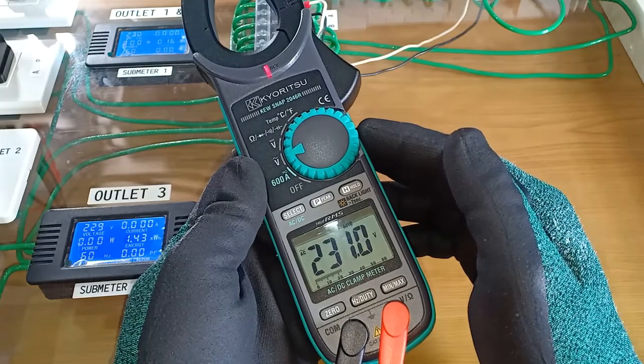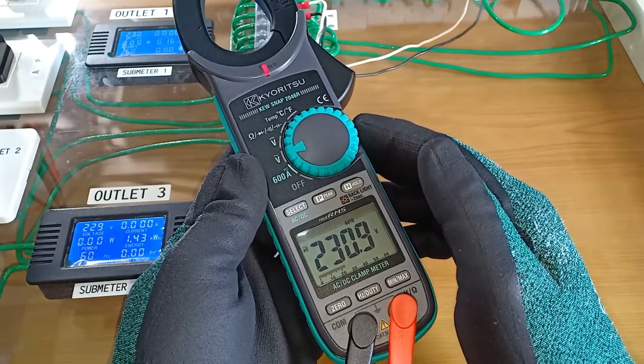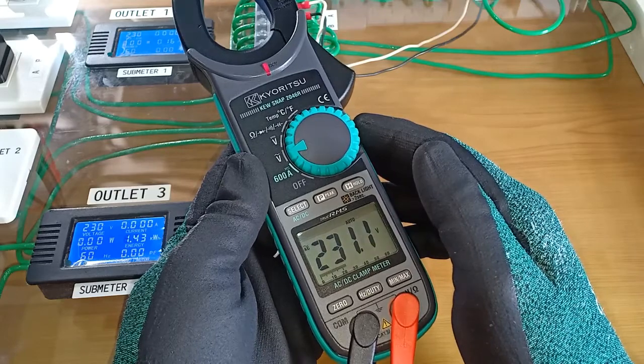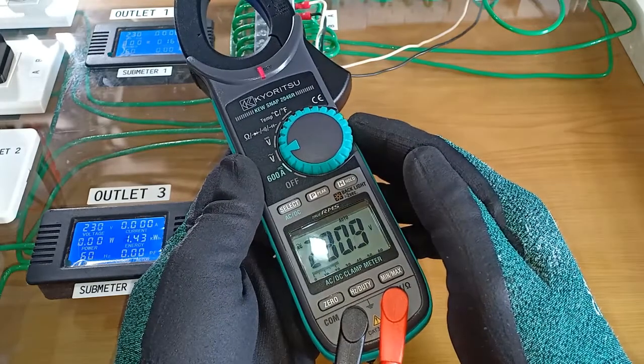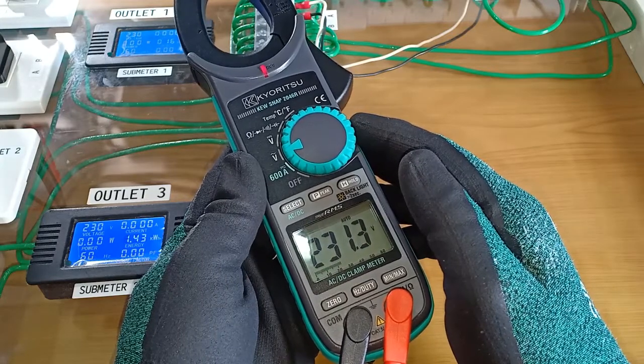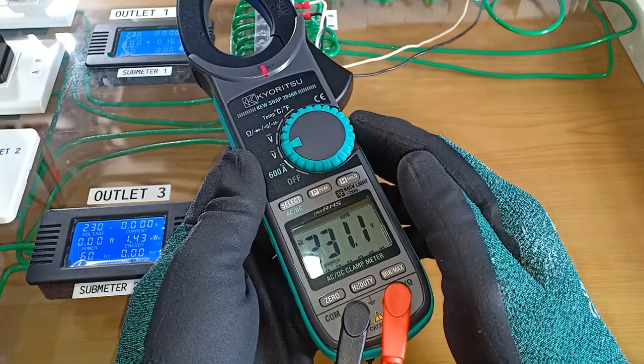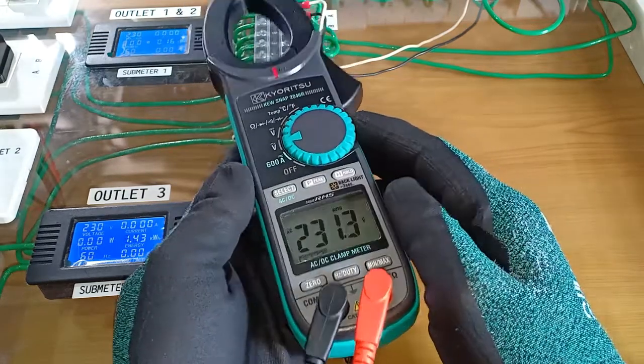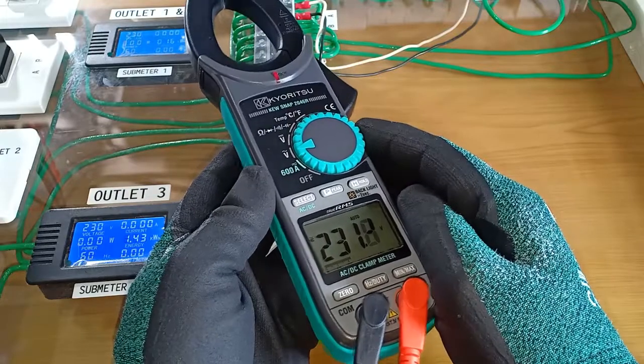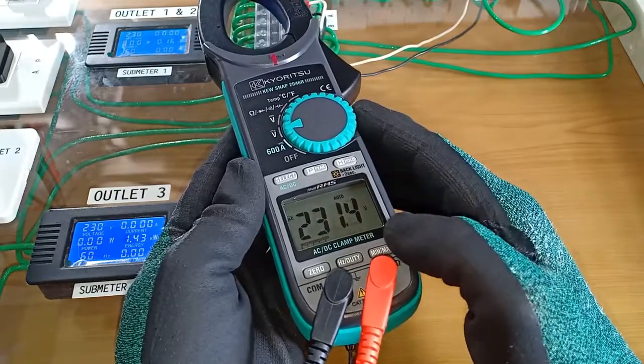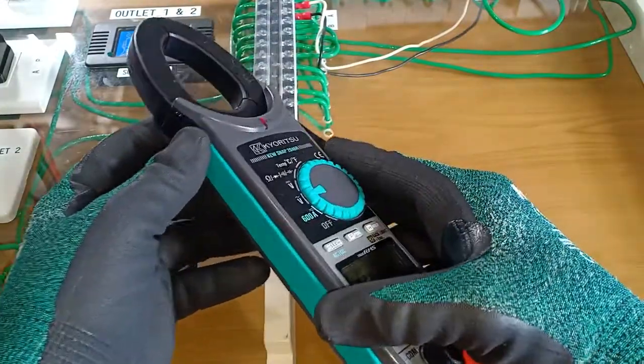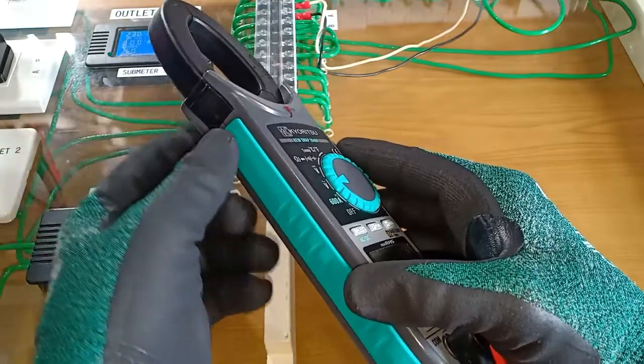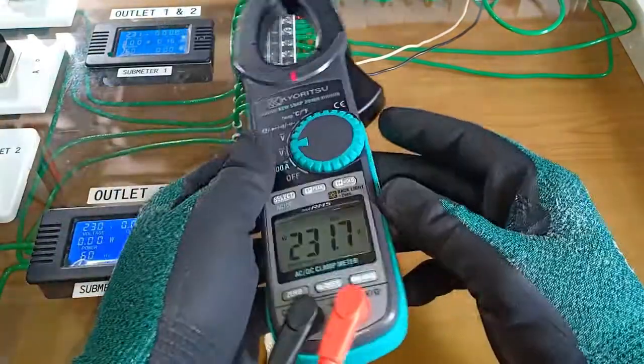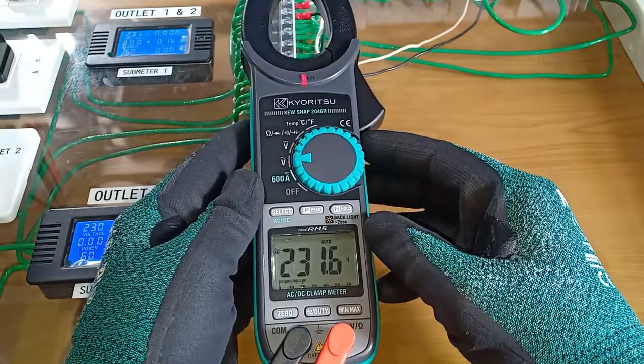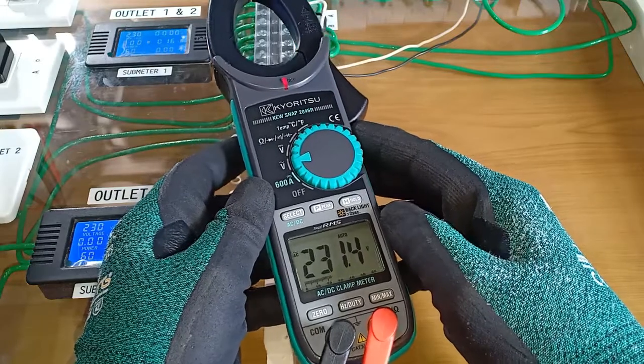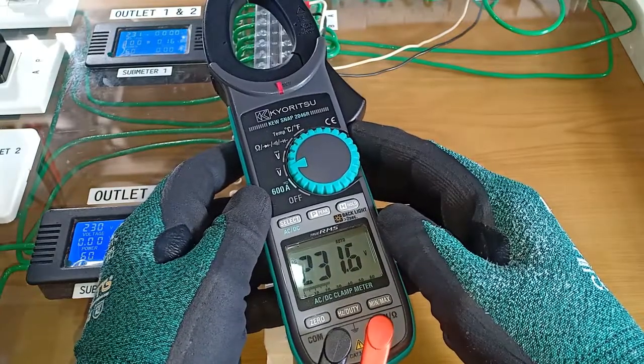An AC-DC current clamp meter is really one of the essential tools in the arsenal of the electrical practitioner who deal with AC power systems and also DC power systems. Overall, in my limited test, I think that the KEW2046R has done rather well. I do hope, however, that the manufacturer in future versions of this device would improve the speed and accuracy of AC current measurement, would install a separate backlight button, perhaps also design a pair of jaws thinner than this, and improve the non-contact voltage detection, and perhaps also include a low-pass filter, which facilities maintenance personnel who deal with adjustable speed drives would certainly appreciate.